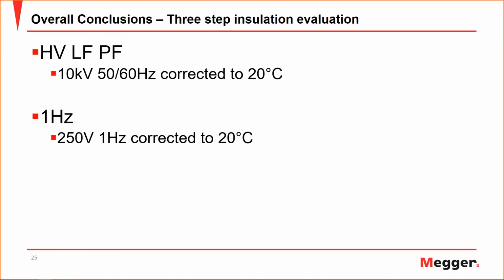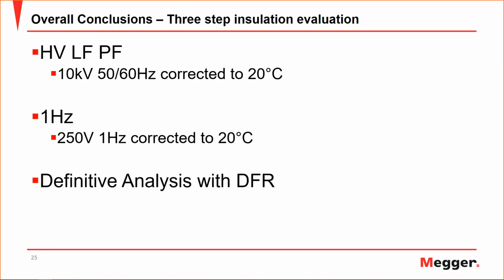This will point you in the direction that you can do further investigation if needed, like in the examples. We did not have to run full spectrum definitive DFR on every single bushing. We only had to do it on 1 or 2, 1 to confirm what the good measurement was, and 2 to confirm when there was a bad 1 hertz value measurement, and to see what is the problem with that particular asset.